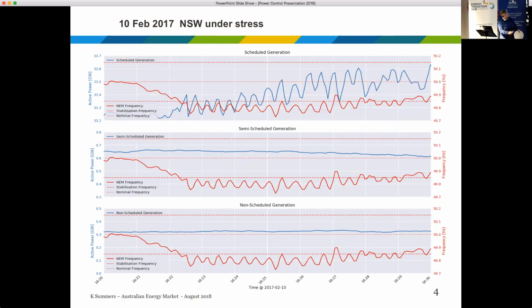The receiver's not working. Okay, so you can see in red the boundaries of the normal operating bands, marked with dotted lines and 50 in the middle, and the red trace is frequency. You can see the actual megawatts dropped down below the boundary of the normal operating band.